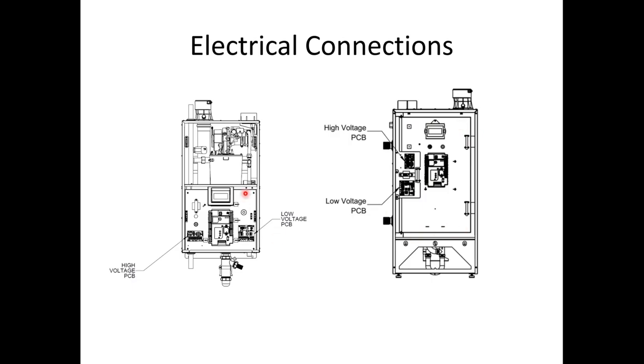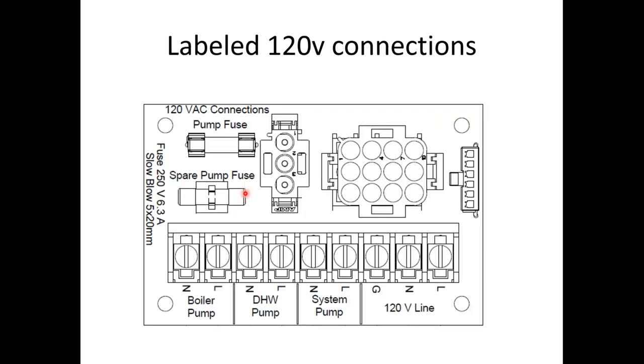Whereas when you take the jacketing off of the wall hung, you have direct access to the heat exchanger and all of the harnesses. Your 120 volt connections are all going to be labeled and fuse protected. The spare fuse comes with them, and there's also an envelope shipped with them that will have the spare fuse. If you're not using one of the pumps, don't worry about it. Just don't wire it. And if you're using a zone panel for domestic hot water priority or anything else, there are wiring diagrams showing how to get full priority if you're not using our Sage panel.